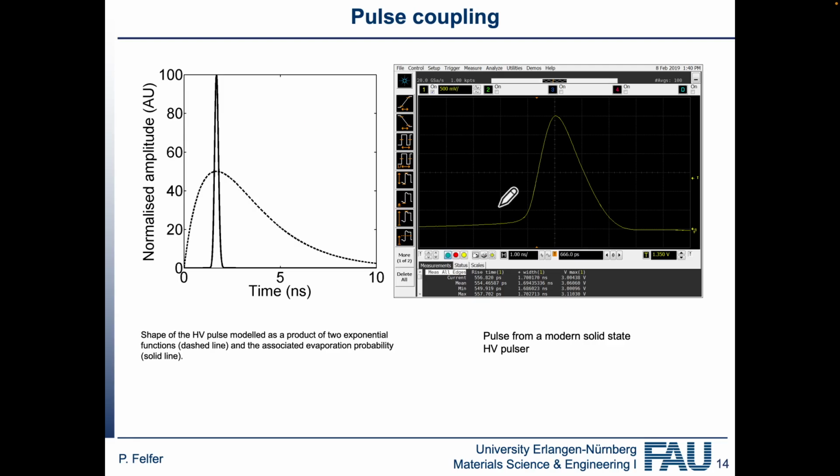So if we have a voltage pulsed atom probe, essentially what we have is a pulse with a typical width of about 1 to 5 nanoseconds. It depends on what kind of pulsar you have. The one that we use in our home built instrument has about 1.5 nanosecond full width half maximum, and it's a very, very good pulsar. But I, for example, have some older pulsars that people just donated to us, where the pulse width would be closer to 5 nanoseconds or something. Why is that important?